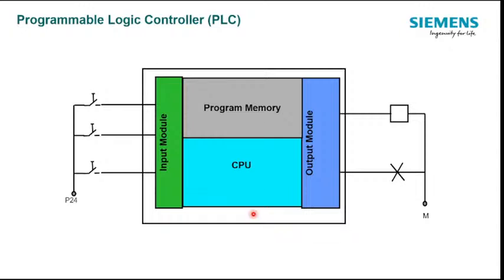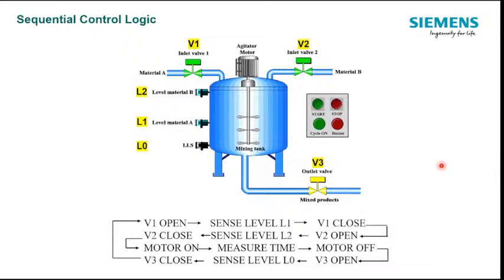A PLC consists of input modules, a CPU along with a program memory area, and then output modules. The input and output modules are used to connect the field hardware devices and control them. So if you take our example using the PLC, when I press the start push button, I want the valve V1 to open, right?